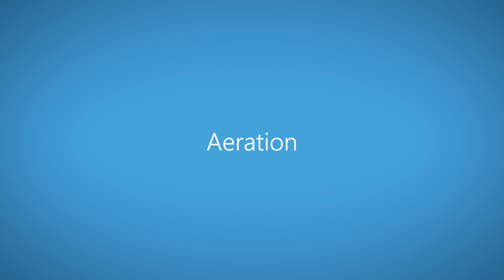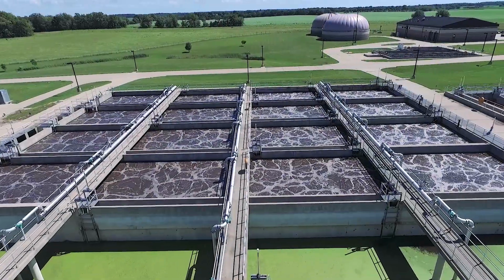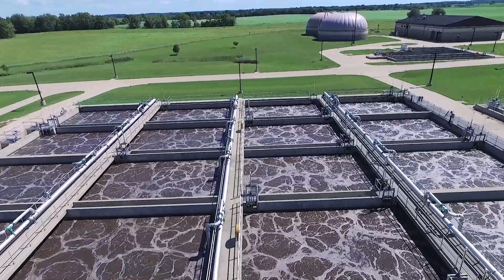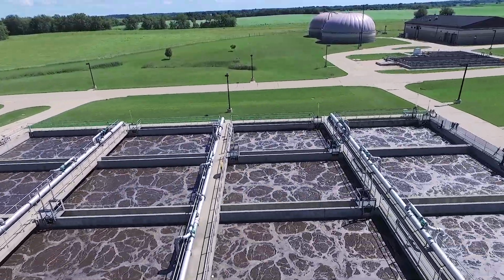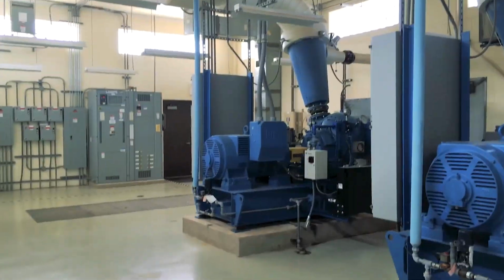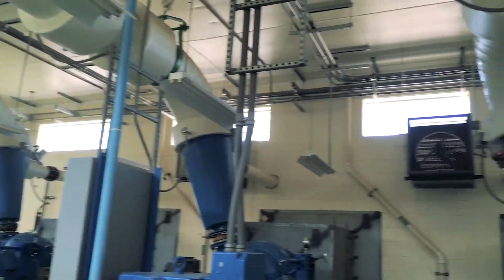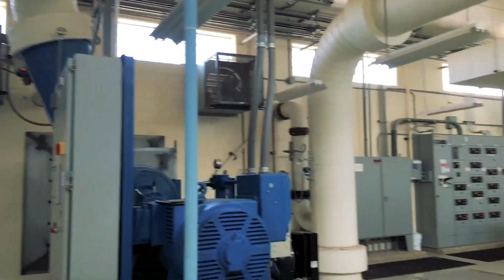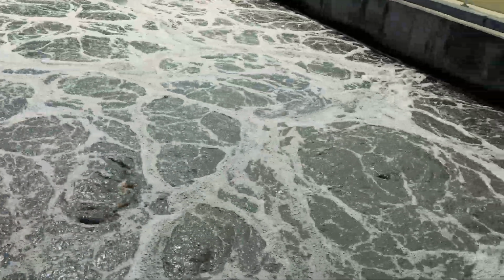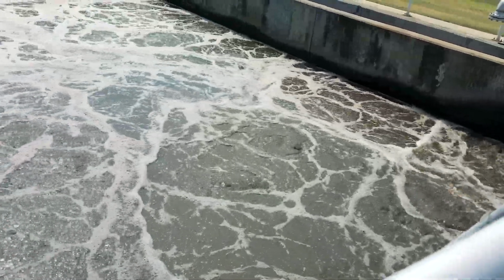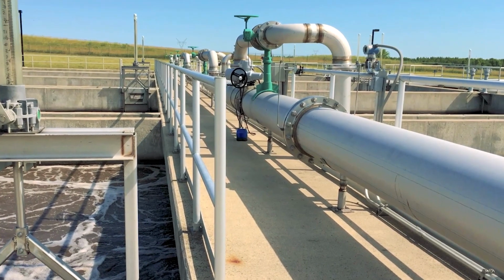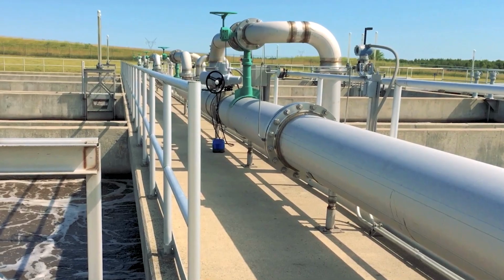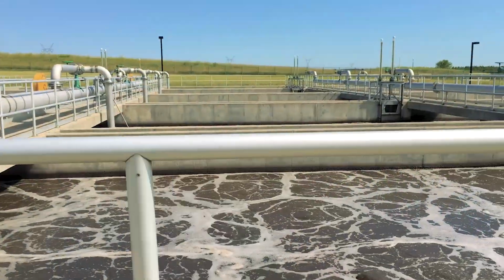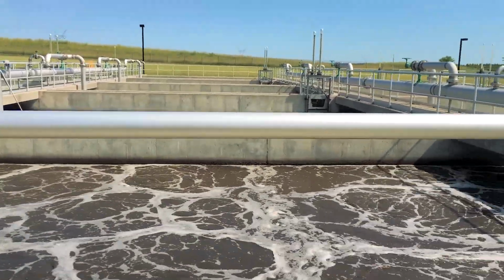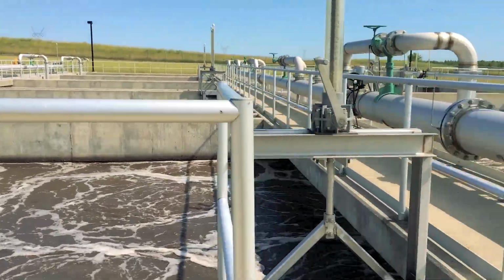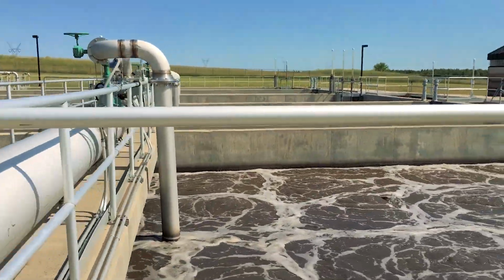The aeration system is designed to provide oxygen to the liquid in the aeration basins to suspend the solids and stimulate the growth of the microbes utilized in the secondary treatment system. Air is supplied to the basins by three 300 horsepower high-speed blowers located in the pump blower building. In each aeration basin, air is fed to three independent aeration zones or service drops. Airflow is measured and locally indicated at each zone, and the airflow can be adjusted via a modulating butterfly valve. Oxygen levels are measured in 2 aeration basins or 6 aeration zones to allow the control of airflow to each aeration zone and to maintain the proper oxygen levels.